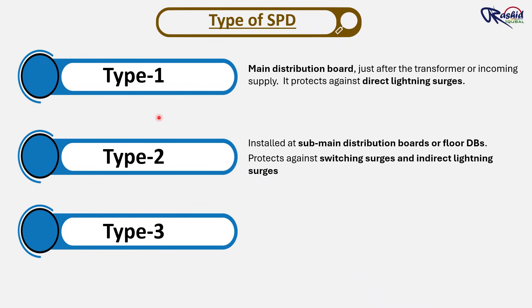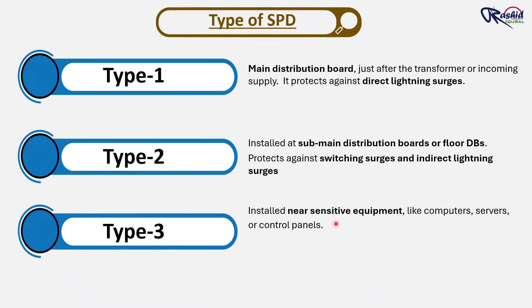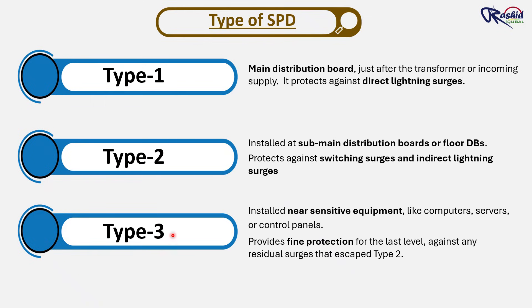Type 2 SPD generally uses MOV technology. Type 3 SPD is installed near very sensitive equipment like computers, servers, or control panels. Even after Type 1 and Type 2 SPDs, a very small amount of surge might still remain. So Type 3 catches the tiny leftover surges and makes sure they cannot damage sensitive loads like server rooms, data centers, medical equipment, or CCTVs.